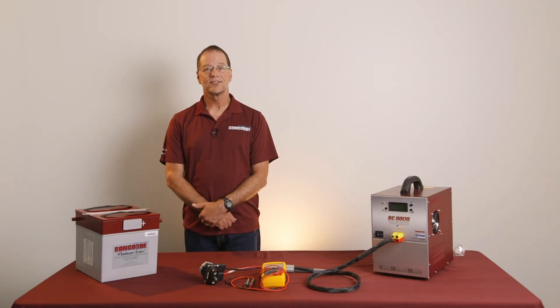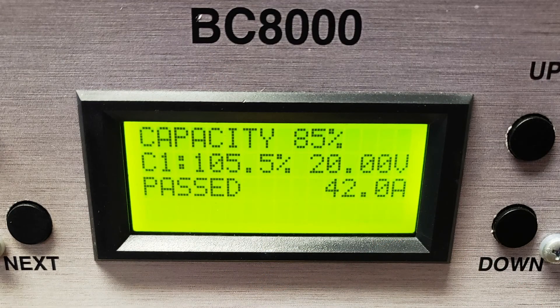The capacity test is finished. On the screen are the readouts from the BC8000 to show you the results. The battery we tested gave 105.5% capacity at the 42-amp rate, which is definitely a pass. The minimum to pass is 85% or 51 minutes at the C1 rate. In the CMM, there is a formula to convert runtime minutes to capacity percentage. If the battery had tested below 85% or 51 minutes, then it would have failed the capacity test. If this happens, you would need to proceed with a conditioning charge and repeat the capacity test. Like the deep discharge recovery procedure previously mentioned, we will go through the conditioning charge procedure in a separate training video.